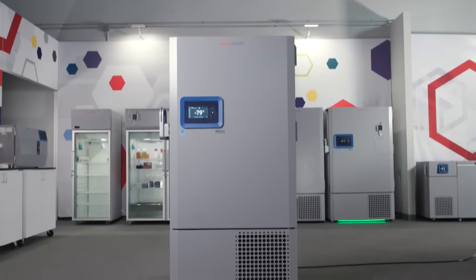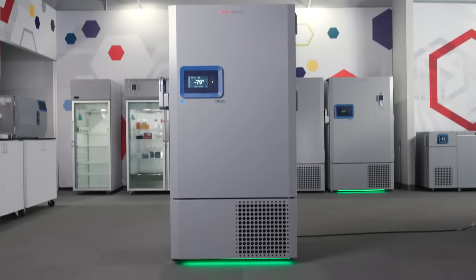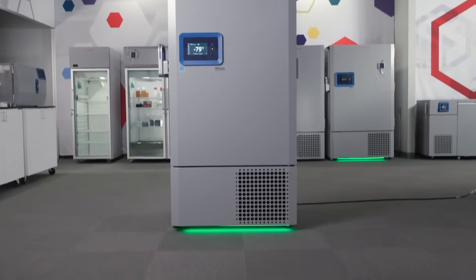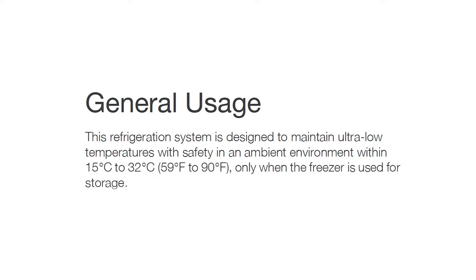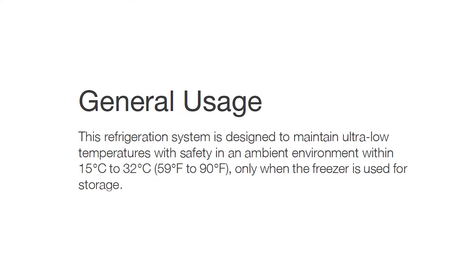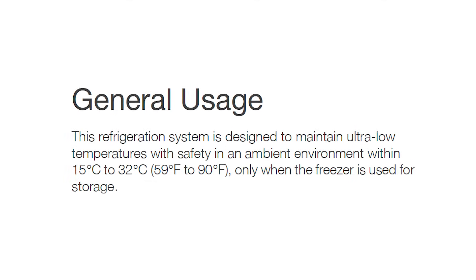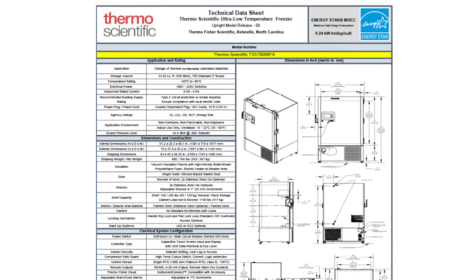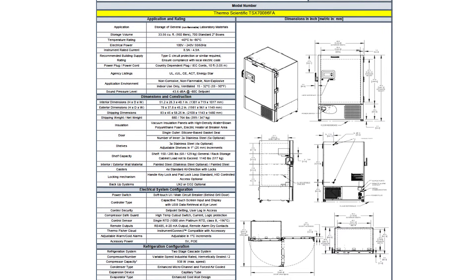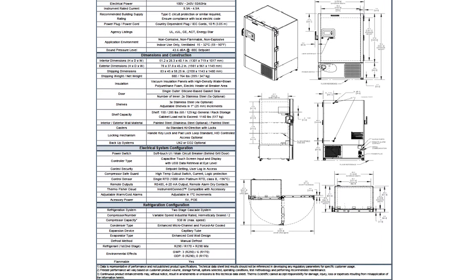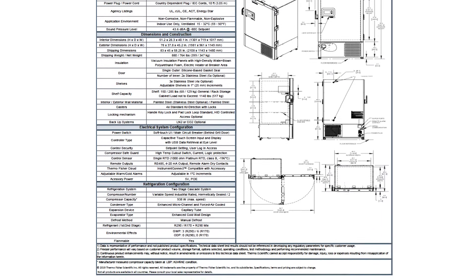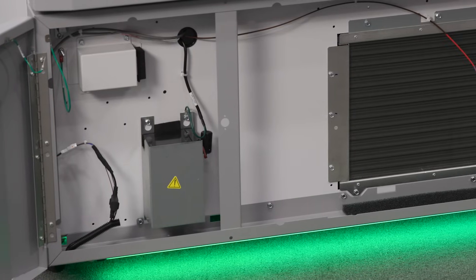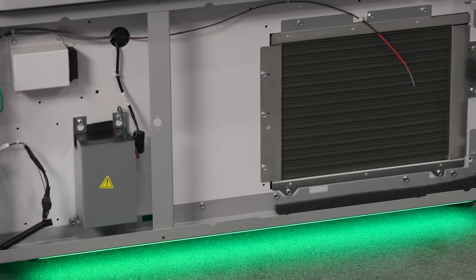You also need to consider the ambient condition of the room where the freezer will be installed. TSX Universal ULT Freezers can operate between 15 to 32 degrees Celsius. Each freezer's technical data sheet discusses the heat output to expect from the freezer, but make sure your room and HVAC system can handle ULT Freezer operation.